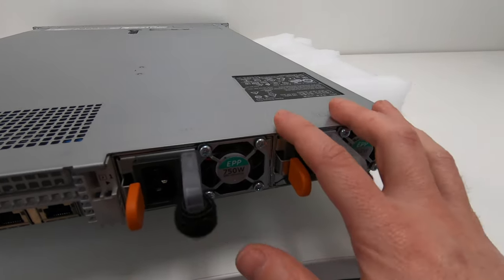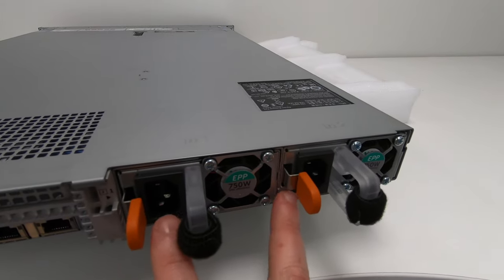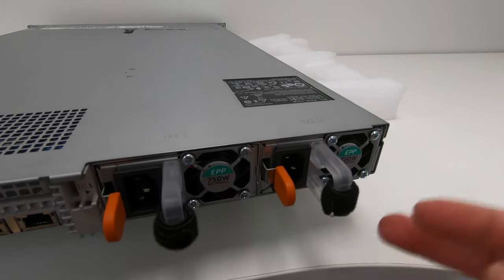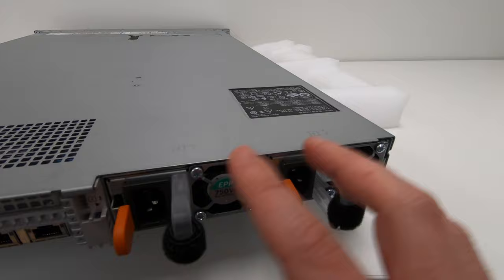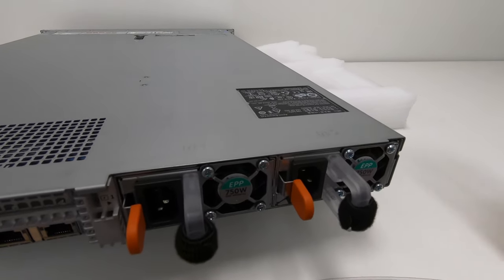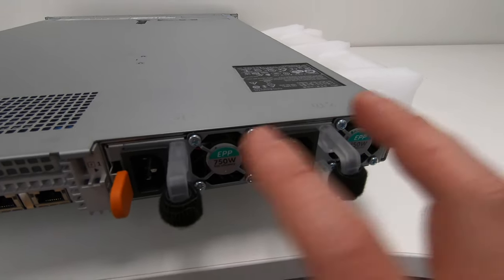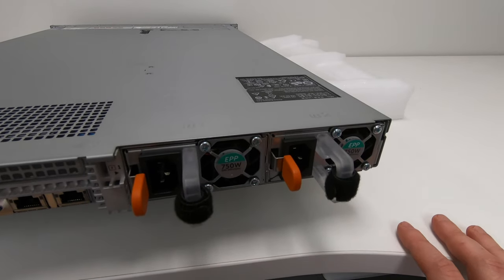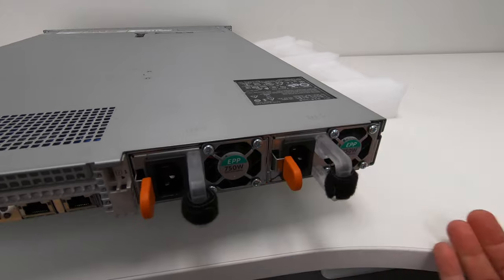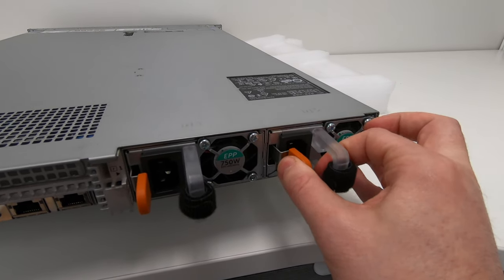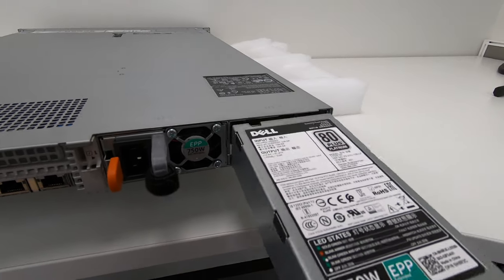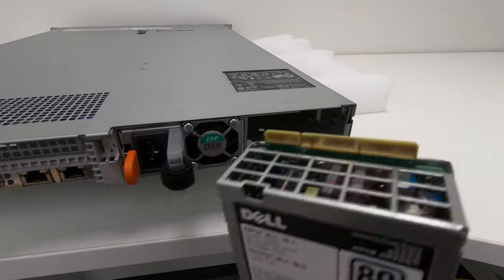We always set them up in pairs. These will be running into two different power sources, so one into one power rail or into a different UPS than the other one, so that if one power rail, one PDU, one UPS goes down, I've got access to the other one. These are easily removable by pulling the little latch here and the whole unit just comes out. I'd buy a brand new one if a particular unit dies and then just slot it in as normal.